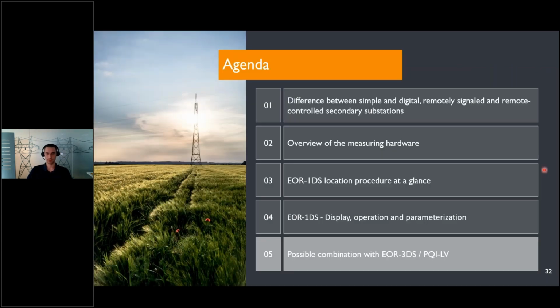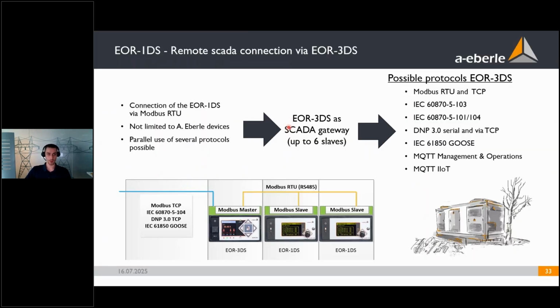So then let's get to the last topic of today, the possible combination of the EOR-1DS with the EOR-3DS or the PQI-LV. This combination could be done to simply have a remote SCADA connection, or also to have a Modbus master-slave system. As you can see here, the EOR-3DS would function as a Modbus master, while the EOR-1DS, or it could be EOR-3DS as well, functions as a Modbus slave. They communicate via Modbus RTU, and then the EOR-3DS will convert this and transfer the data via an IEC protocol or DNP3 or Goose.